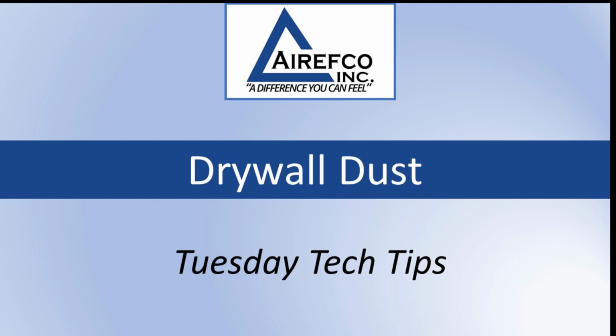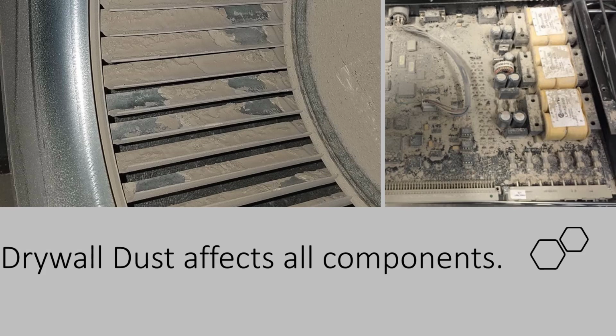furnaces to dry out drywall. Why is there so much drywall dust caked inside this motor? Drywall dust affects all the components in a furnace or a fan coil. The blower wheel, the motor, electronic circuit boards, everything.